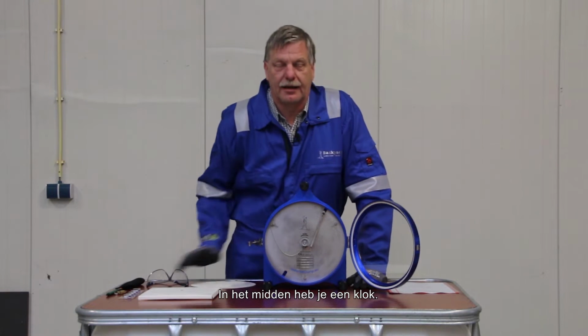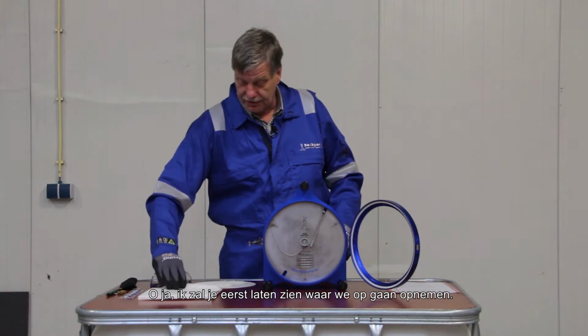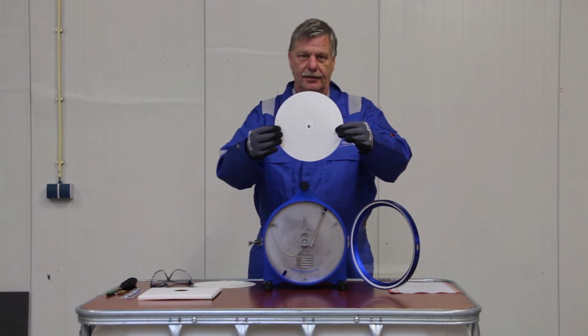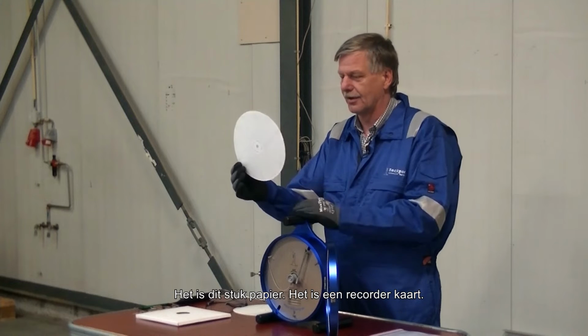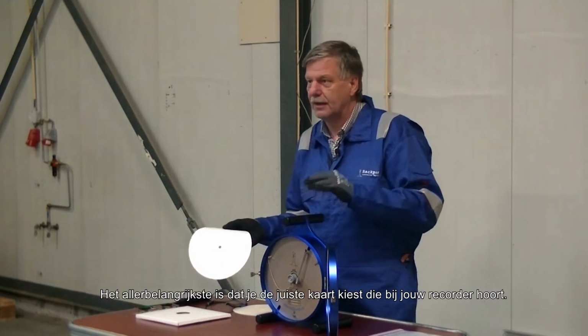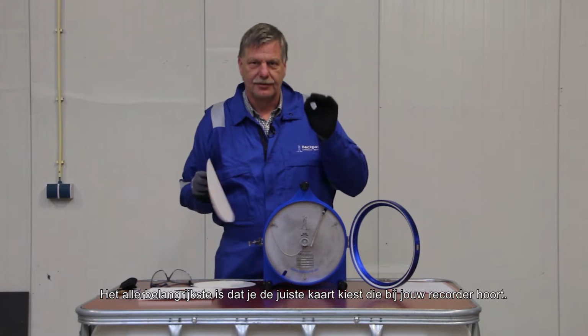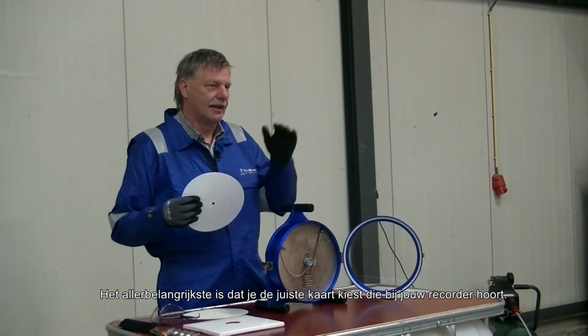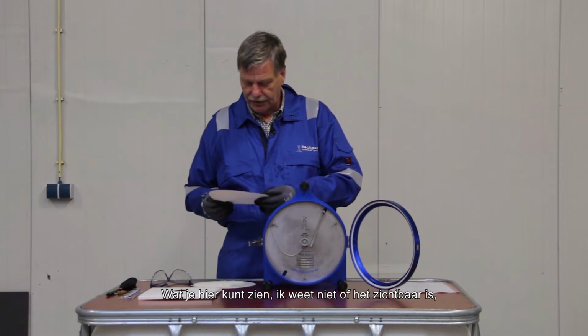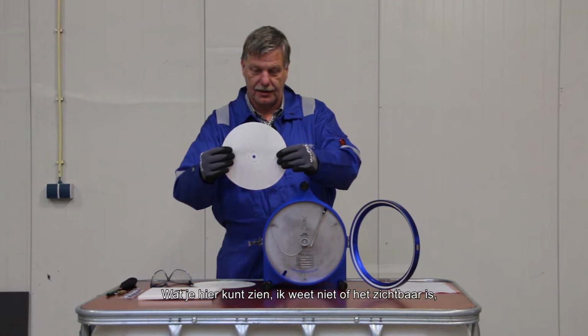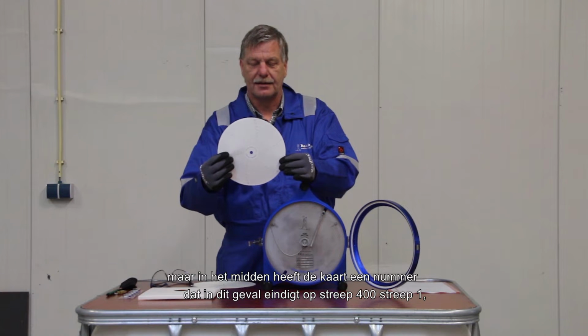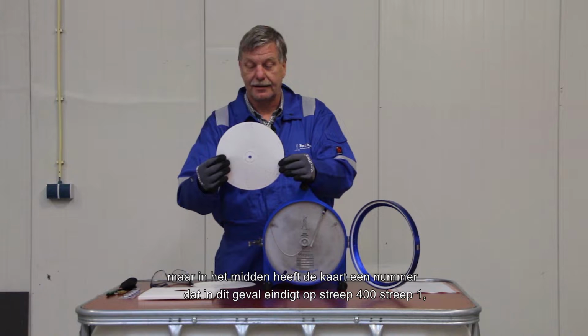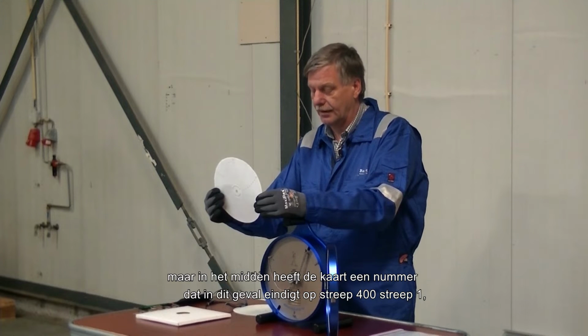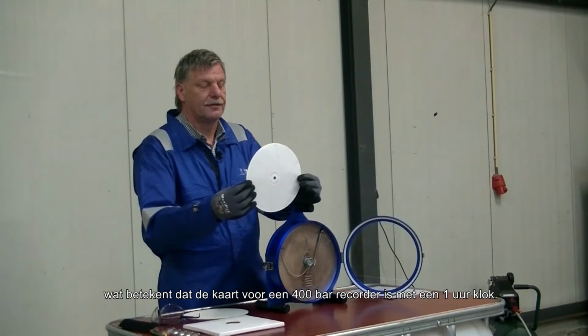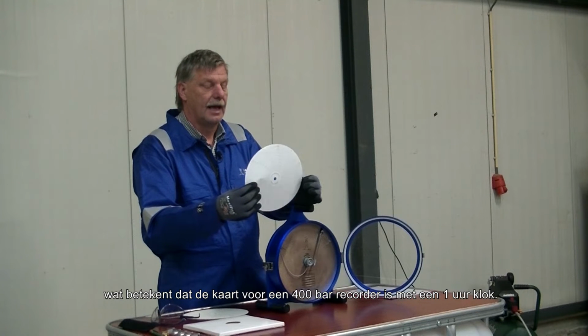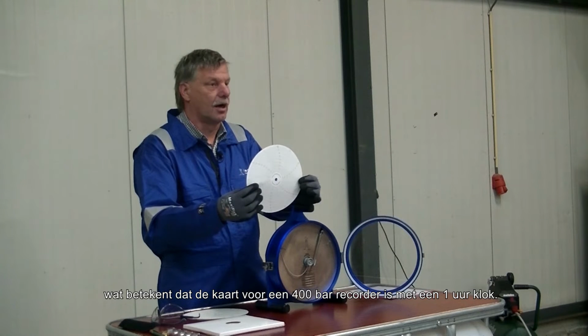In the center you've got a clock. Let me first show you what we're going to record upon, this piece of paper. It's a circular chart. What's of utmost importance is that you select the correct chart that matches your recorder. In the center, the chart has a number that ends, in this case, with -400-1, meaning the chart is for a 400 bar recorder with a 1 hour clock.